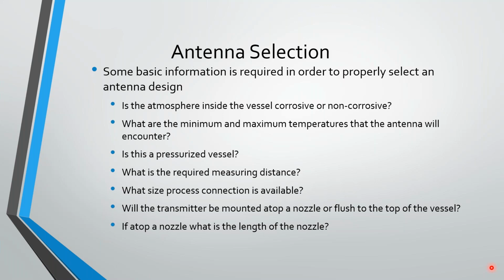Distance will help us choose the right one there. What size is the process connection? That's important too. So say we've got a tank with a process connection that's 4 inches - well, obviously we can't use a 6-inch diameter antenna. It's just not going to fit through that hole.